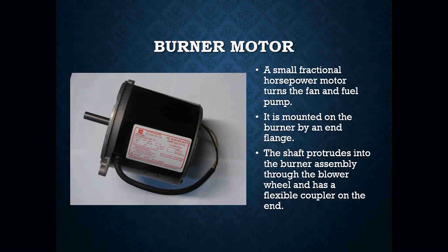Your blower motor is usually a small fractional horsepower motor, somewhere around a quarter horsepower. That motor is going to be used to turn the blower wheel and spin the fuel pump. It is mounted on the burner by an end flange and the shaft protrudes into the burner assembly through the blower wheel and has a flexible coupler on the end.